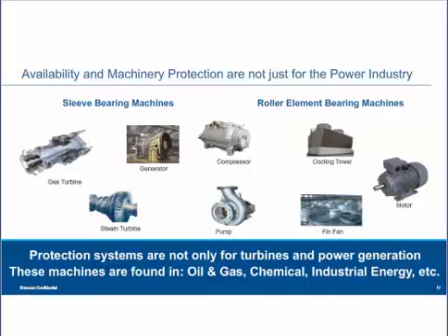Okay, so effectively going back to the presentation and the question, you've got two different systems. Generally, you have a protection system, and then as people are really grasping the reliability concept and trying to make their plants more reliable, you get people starting to use more prediction capability as well. So effectively, in the past, you would have to take that signal from your protection system and pass it in some way, whether it's hardwired or across a backplane or what have you, over to a prediction system. So you would wind up basically buying two separate systems in order to get the best of both worlds.